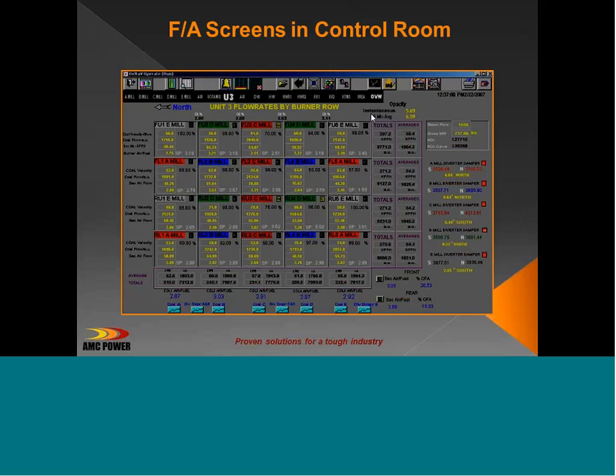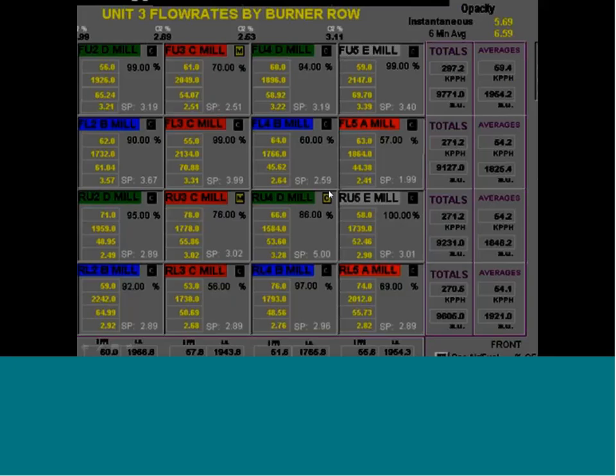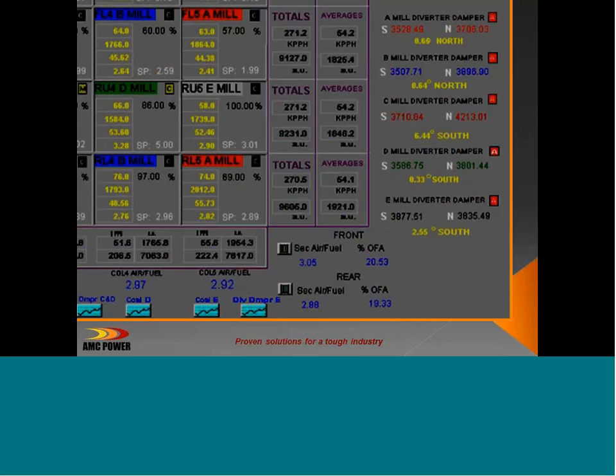So I've gone through two different technologies to show you that we can measure coal flow in each burner line, and we can measure secondary airflow in each burner. We can take the airflow and divide it by the fuel flow and come up with an air-to-fuel ratio. Down here at the bottom, this is an opposed wall-fired unit, so we're looking at two wind boxes. We come up with an air-to-fuel ratio for the front wind box and one for the rear wind box. This is the average air-to-fuel ratio based upon all the mills that are in service.